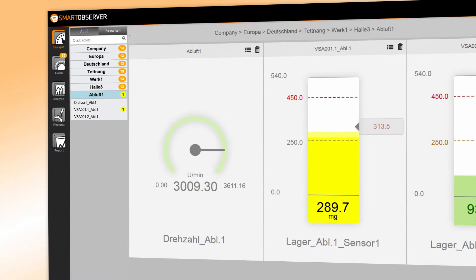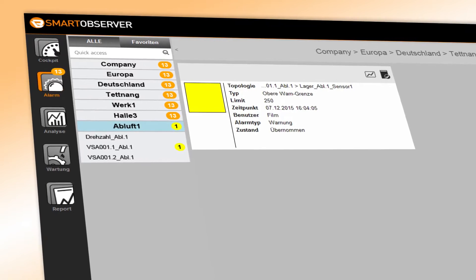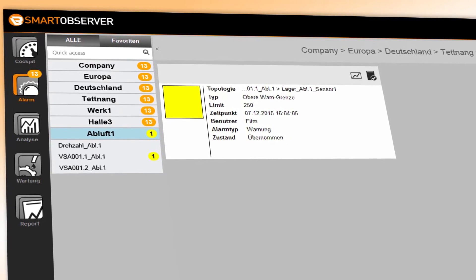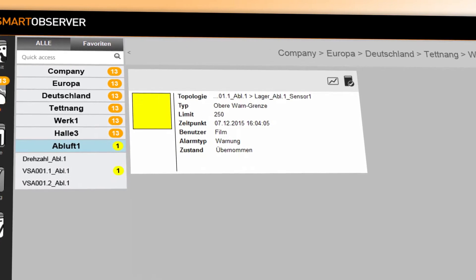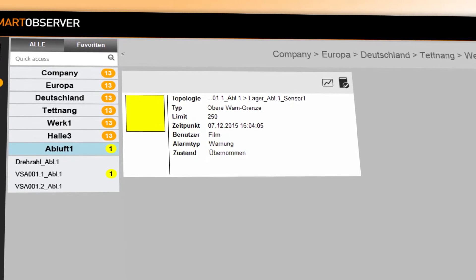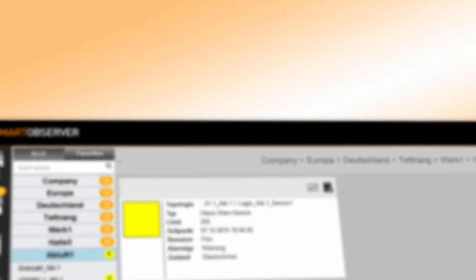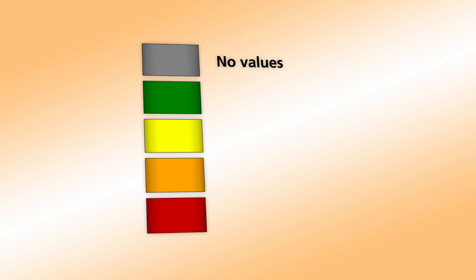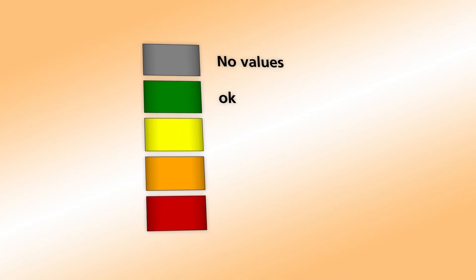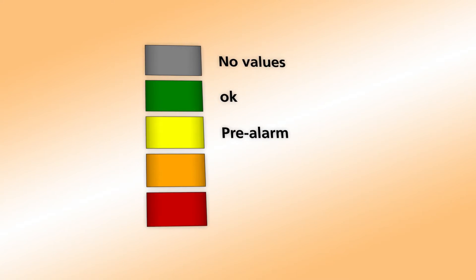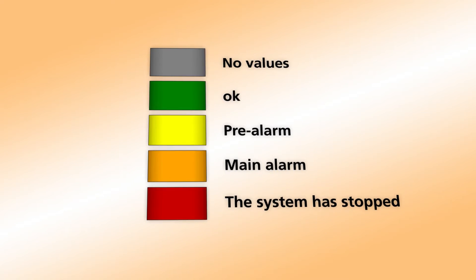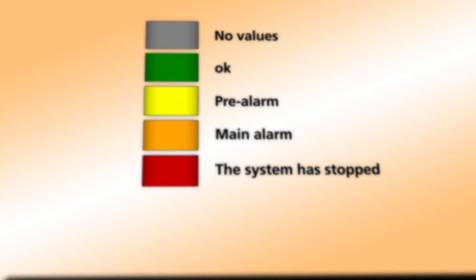Regarding the concrete alarm: the vibration sensor of an individual ventilator is reporting a pre-alarm. All messages are highlighted in standardized colors. Gray equals no values. Green equals OK. Yellow equals pre-alarm. Orange equals main alarm. Red means the system has stopped. Each alarm generates a ticket.